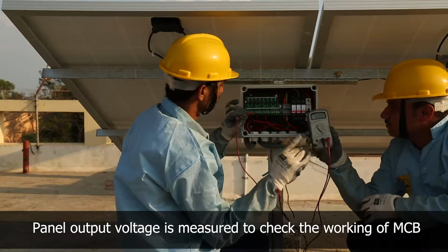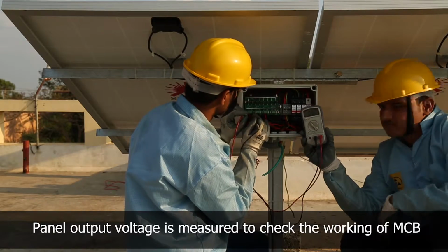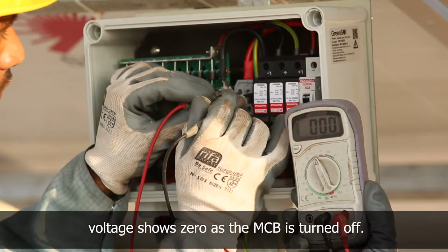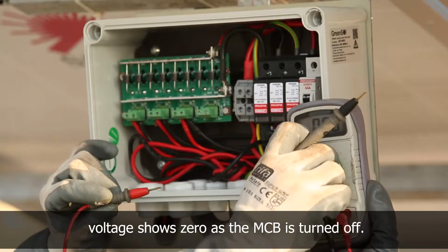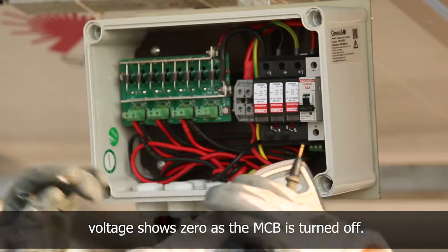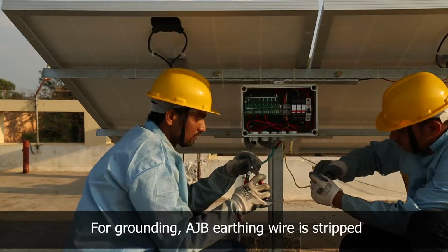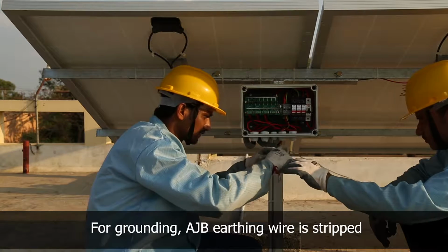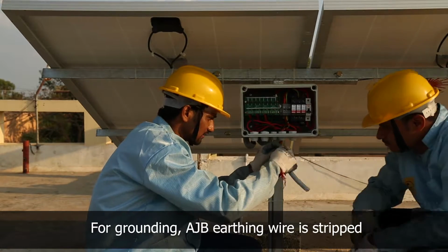Use a multimeter to check the output voltage of the panel. Ensure that the reading shows 0 as the miniature circuit breaker is turned off. This shall confirm that the miniature circuit breaker is in working condition.